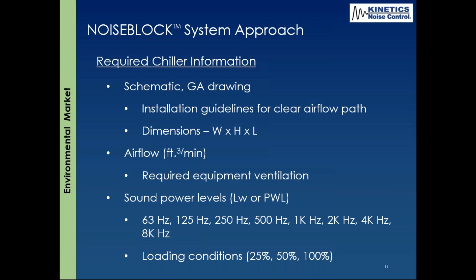It's not that the manufacturer's data is wrong. It's just that the manufacturer's data is under ideal laboratory conditions. You don't have that. You have field conditions. So the acoustical consultant usually will take readings, and then we'll use both, take the highest in each octave band, and that'll be our design spectrum for our noise control.